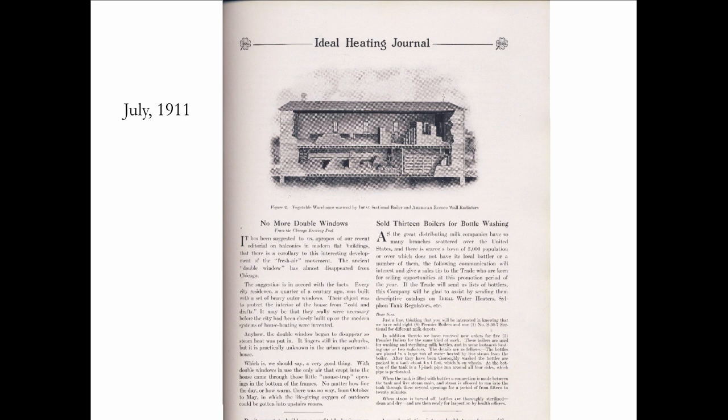So if the heat loss of the room is 10,000 BTUs and the radiator is putting 10,000 BTUs into the room, it really doesn't matter where it is. The reason why it winds up under the window is because they were using these loose windows that allowed fresh air in, and having the radiator right there would warm the air as it came through the window. So there's a little bit of history for you — it helps to study history when you're trying to learn about this old stuff.